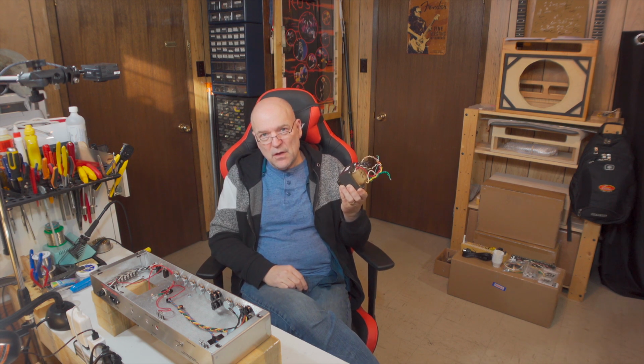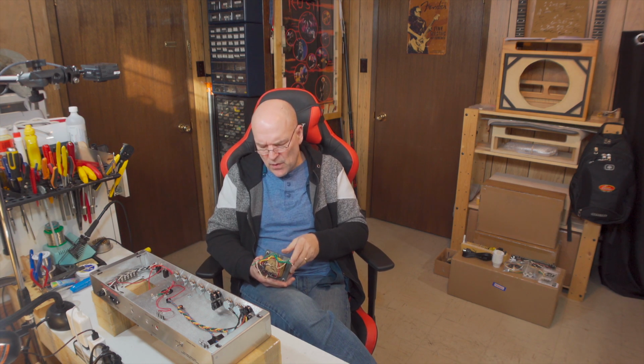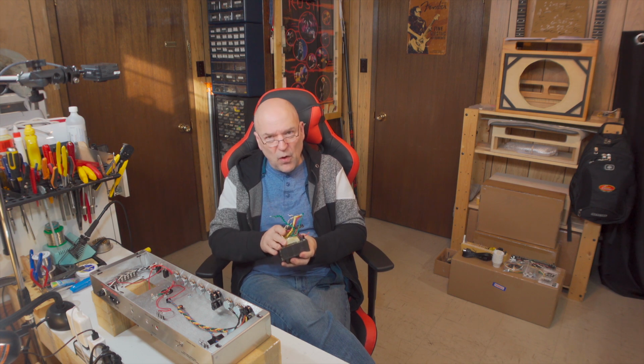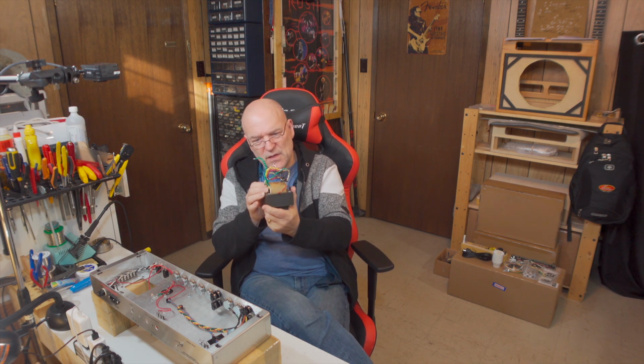Now, by way of a bit of explanation, of course, I'm wearing different clothes because that all happened a week ago. You're seeing this video actually two weeks after the fact. What you want to do if that ever happens is, once you have safely disconnected the power, as soon as you can, do a visual inspection on the transformer or whatever part you think is faulty or having a problem. The reason you want to do that right away is that visual inspection is important, but also you want to feel the component.